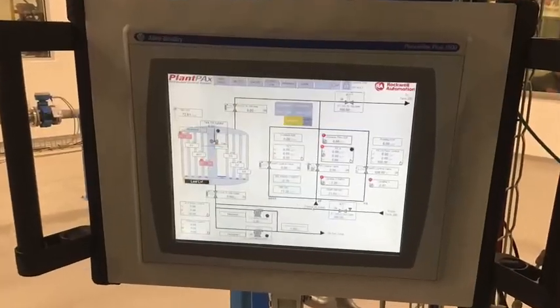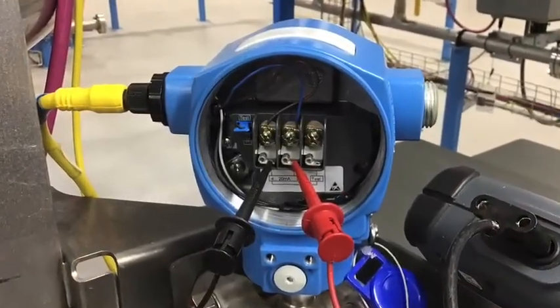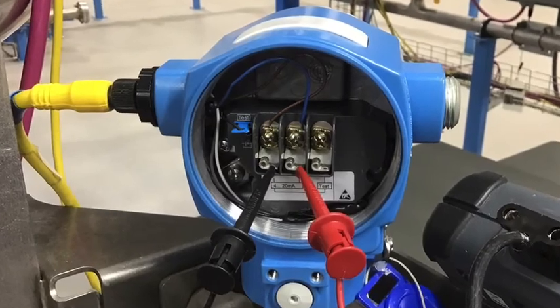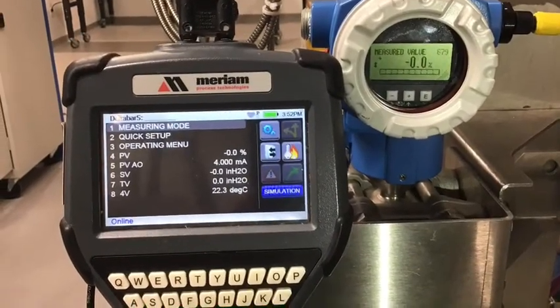Our HART device is Meriam and our PLC is an Allen-Bradley Process Automation System. Connect the Meriam across the input power terminals of the transmitter. Polarity of this device is not a concern. The HART device now becomes a window into the transmitter.